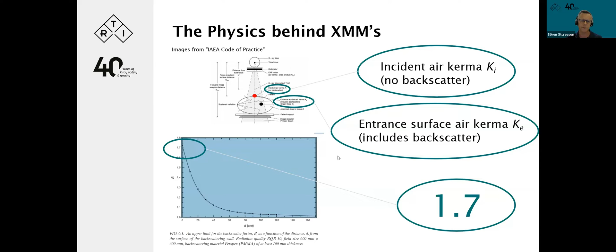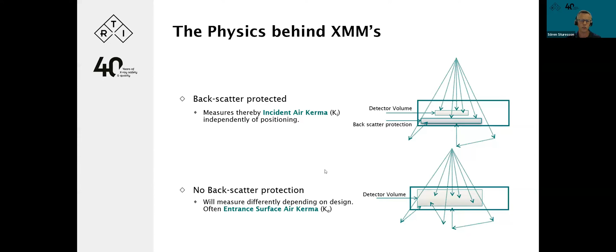Looking into the IAEA Code of Practice, presenting data from there, you find factors that are 1.7. So 70% higher dose due to backscatter if you have a high energy and large field size. So this is important to be aware of, and it's also extremely important in terms of the design of X-ray multimeters. A little bit more about this backscatter protection. This is more or less how it's solved. Then one protects the detector from backscatter. Actually, you protect it also from side scatter to avoid scattered radiation into the detector.